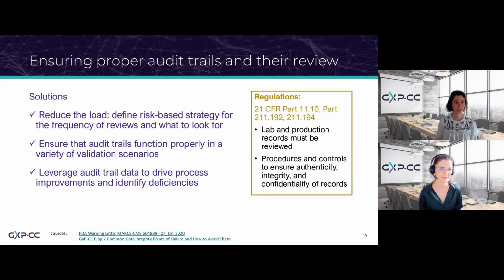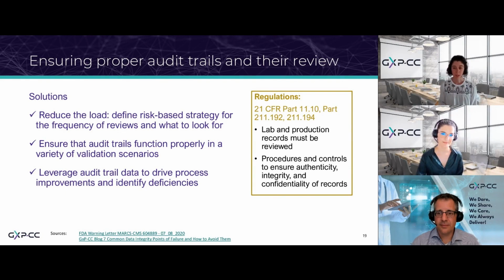Yeah, we were talking earlier about really ensuring a variety of validation scenarios. I recently had an experience where we found the audit trail generally is working, but in specific validation scenarios, we did some stress testing, and we discovered that just for the units, under certain conditions, the audit trail was not working. If we hadn't been able to come up with those scenarios and really do that kind of testing ahead of time, we would have run into that in production instead. So it can be a big benefit to get to that up front, for sure.